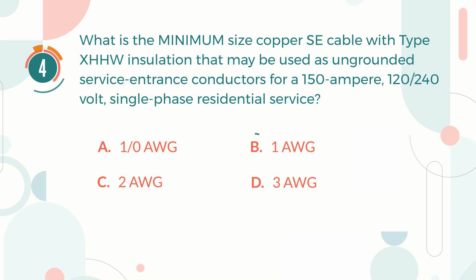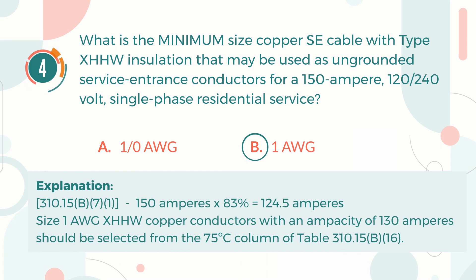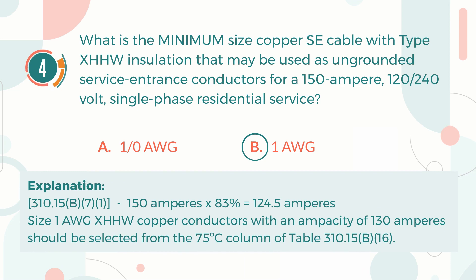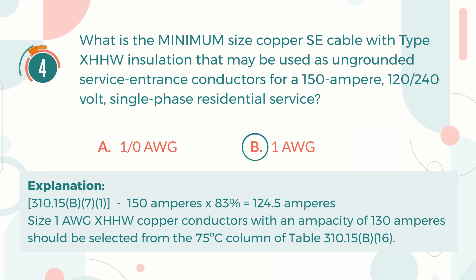The correct answer is B. 1 AWG. Explanation: According to Section 310.15(B)(7), the demand current is calculated as 124.5 Amperes. Hence, size 1 AWG XHHW copper conductors with an ampacity of 130 Amperes should be selected from the 75 degrees Celsius column of Table 310.15(B)(16).